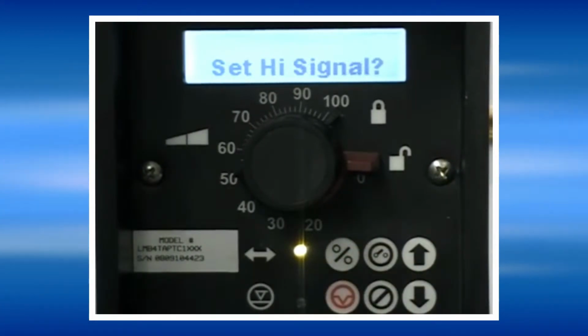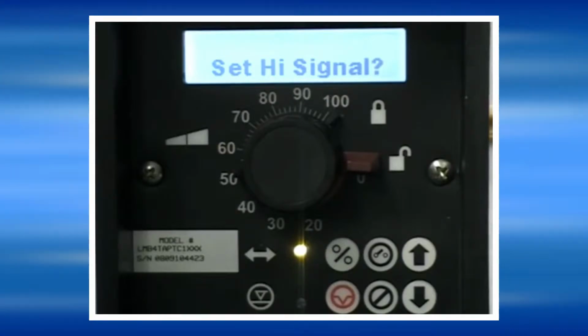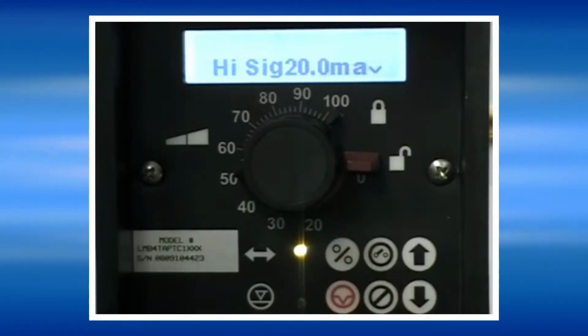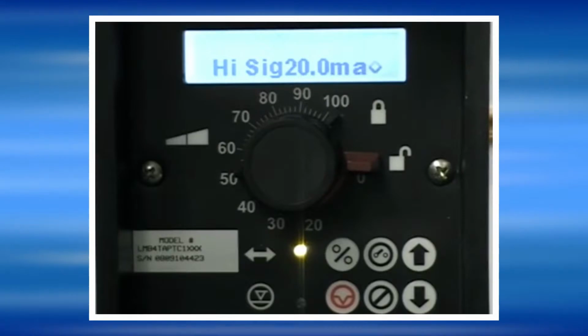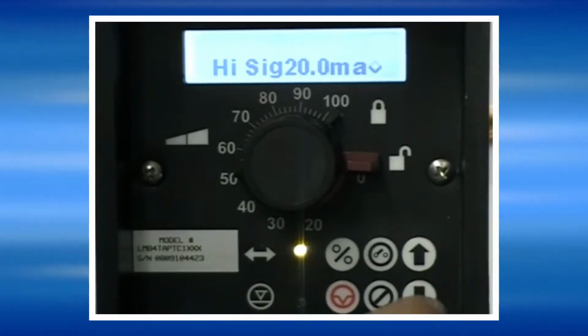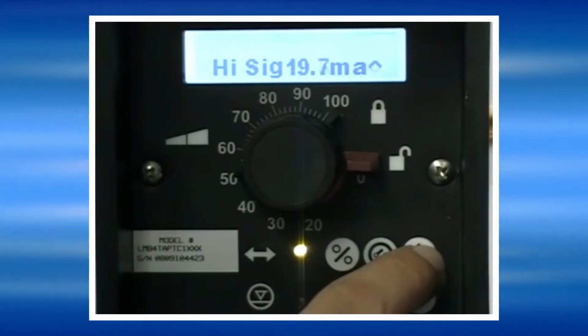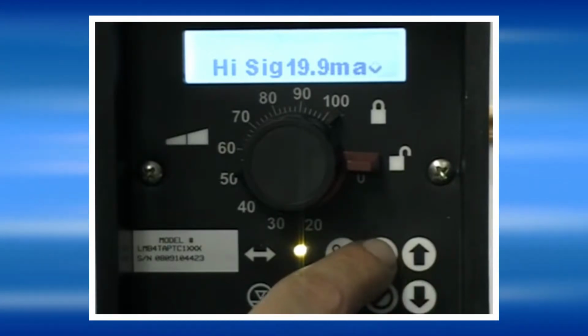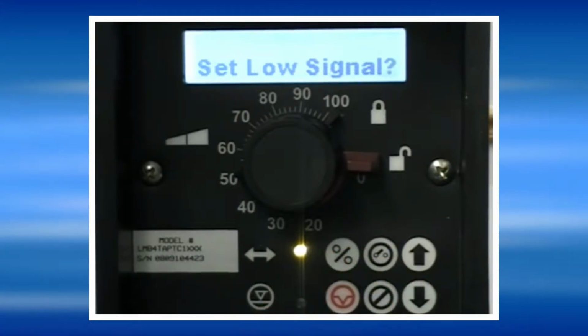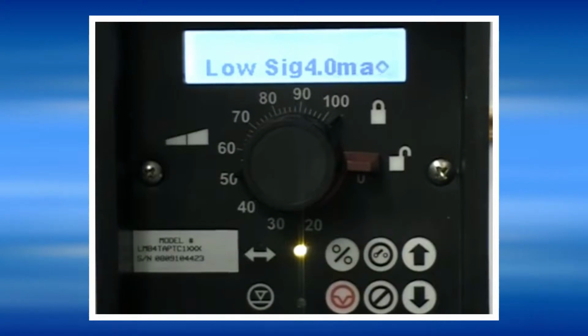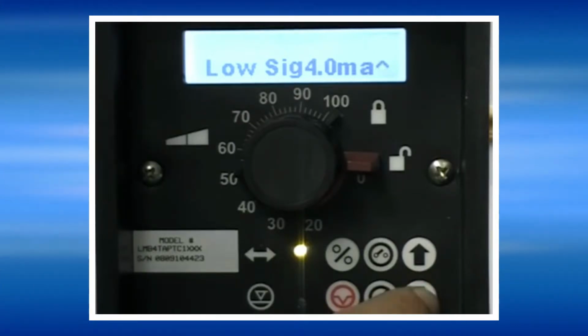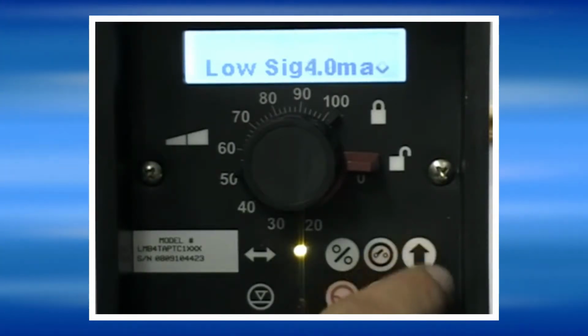Set the low rate setting, and the pump will now prompt us to set the high signal setting. This is the milliamp signal that the pump will run at the high rate for, which can be changed using the up and down arrow keys. To set the low signal setting, you are setting the milliamp signal that will cause the pump to run at the low rate setting that we set previously. Again, this can be changed with the up and down arrow keys.